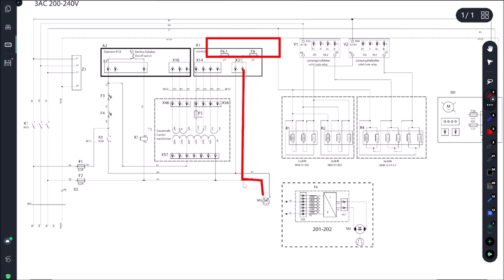We go up to the transformer K1 coil. This is our main incoming off the F2 fuse. On our other side here, same thing - cooling fan coming through our K1 contact through some safety limits all the way back around into our coil.